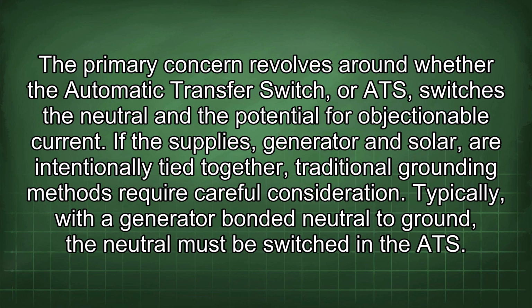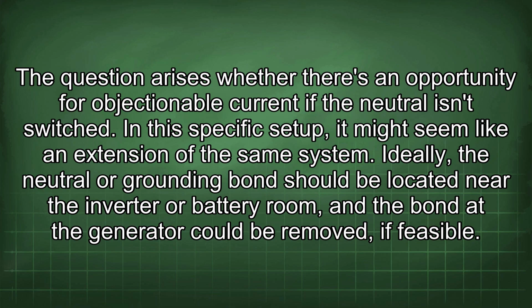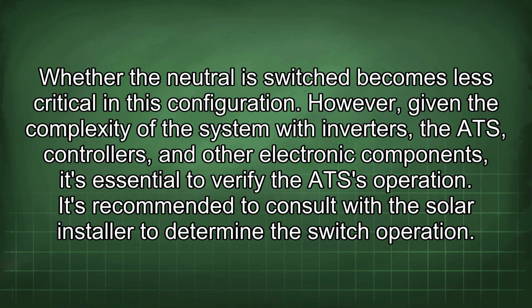Typically, with a generator bonded neutral to ground, the neutral must be switched in the ATS. The question arises whether there's an opportunity for objectionable current if the neutral isn't switched. In this specific setup, it might seem like an extension of the same system. Ideally, the neutral or grounding bond should be located near the inverter or battery room, and the bond at the generator could be removed, if feasible. Whether the neutral is switched becomes less critical in this configuration.